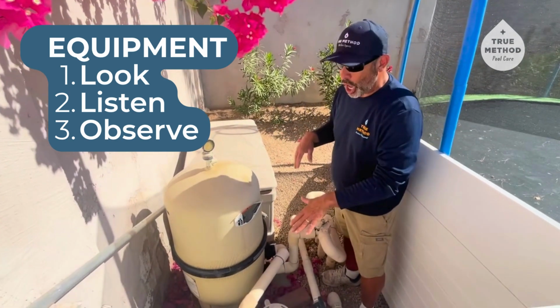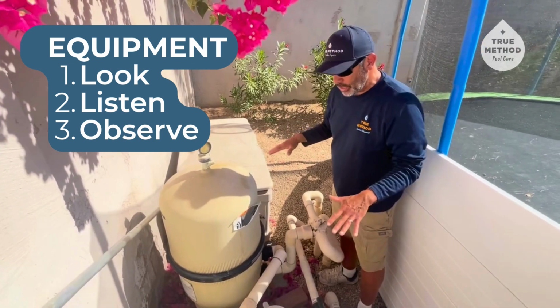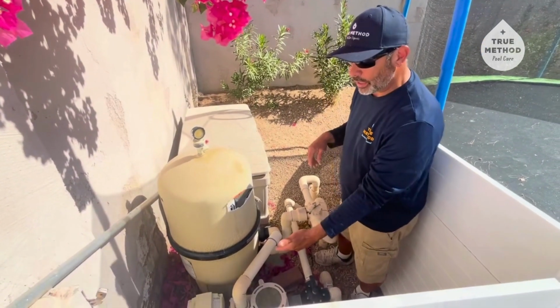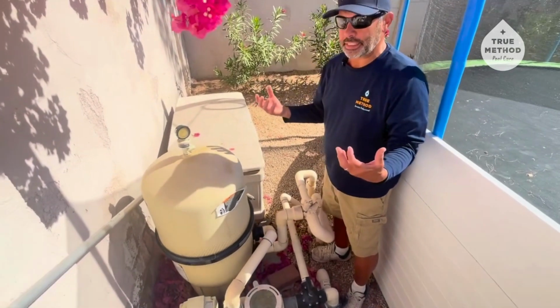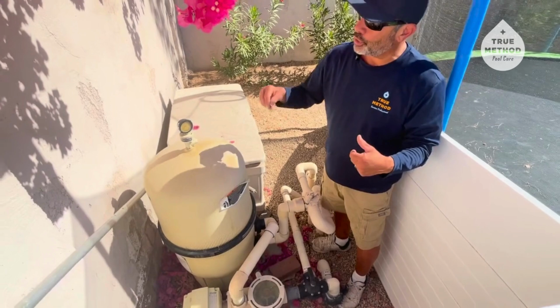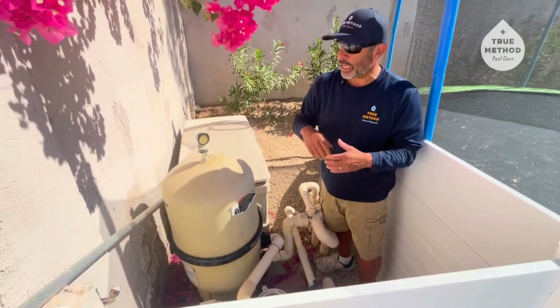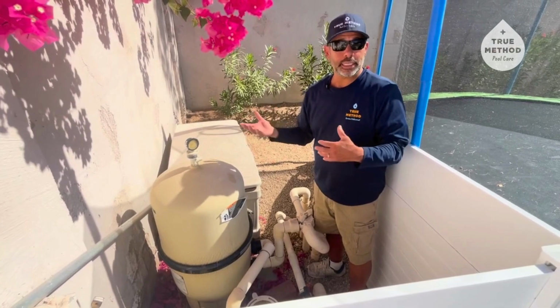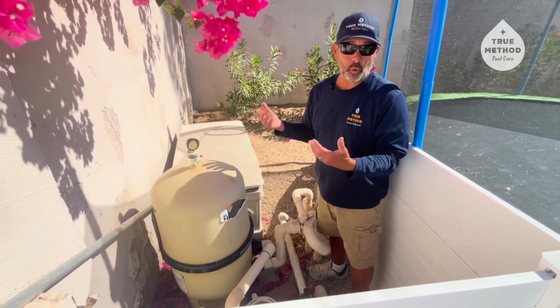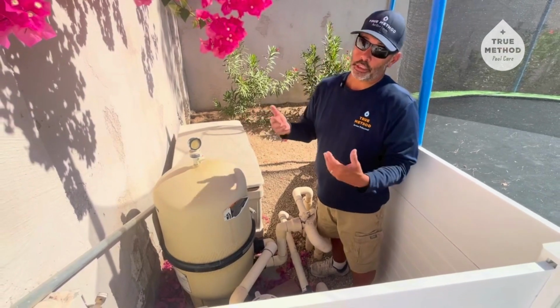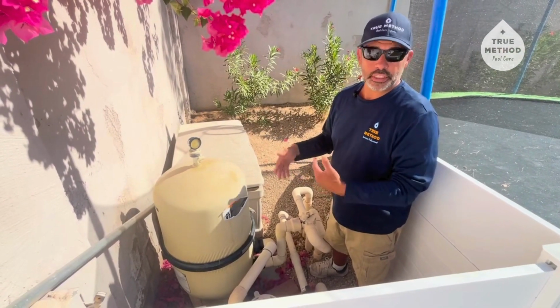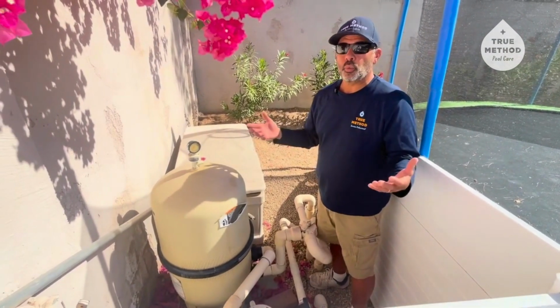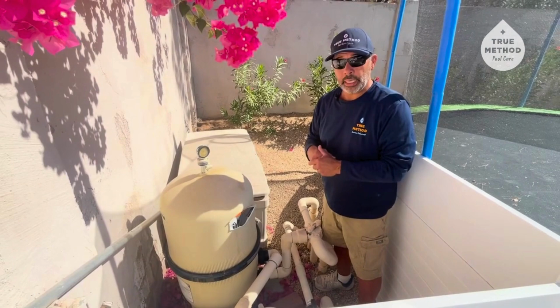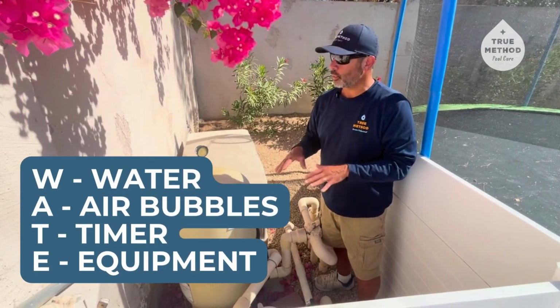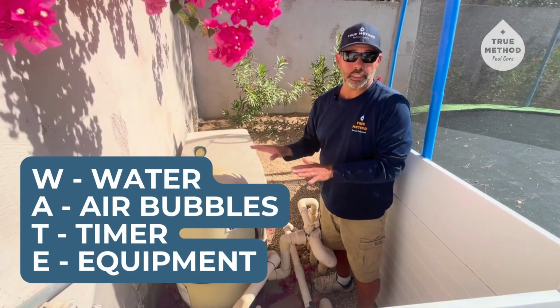So turn your system on, look around to see if you see any air leaks, see if debris needs to be cleared from the motor, listen to the motor to see if it sounds healthy, and observe. Observe your PSI gauge. Your PSI gauge will give you an indication if your filter needs to be cleaned or backwashed. If the PSI is low, you might have an issue with your system somewhere. So again, we're just teaching you what to look for real quick. We have other videos on how to properly diagnose the issue.